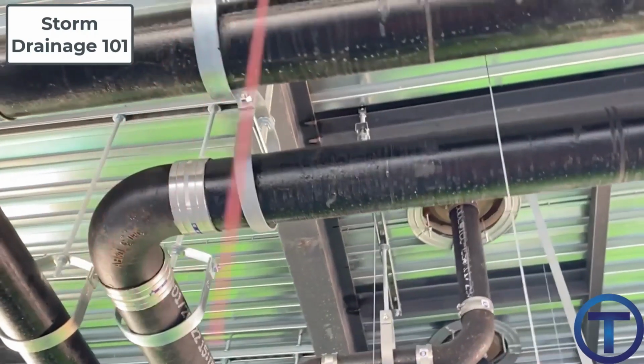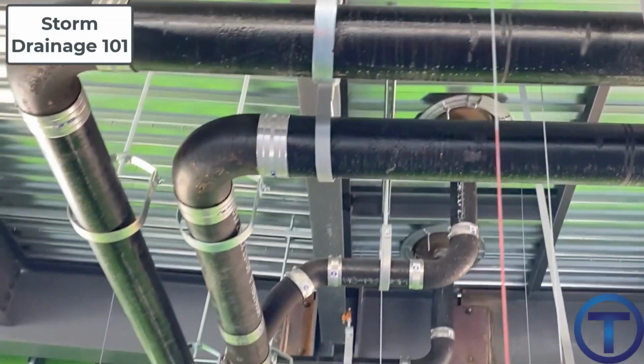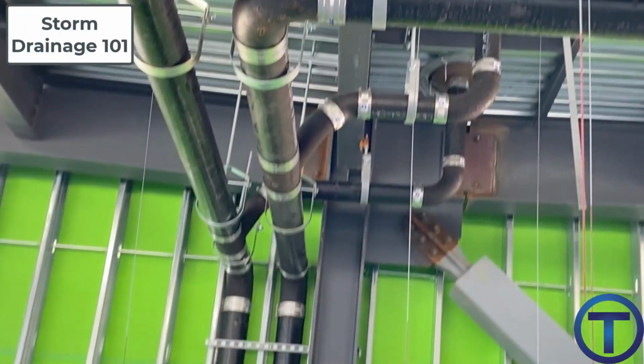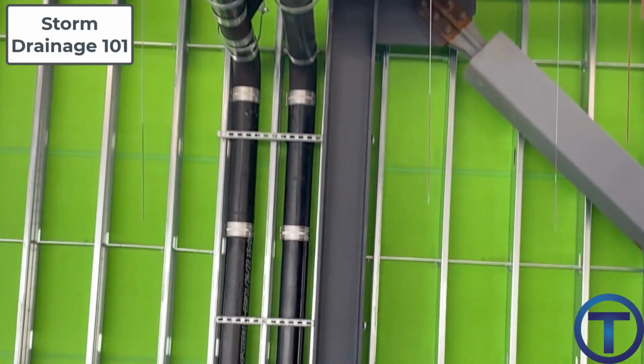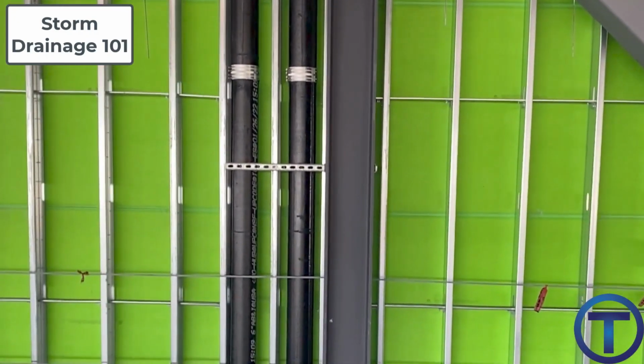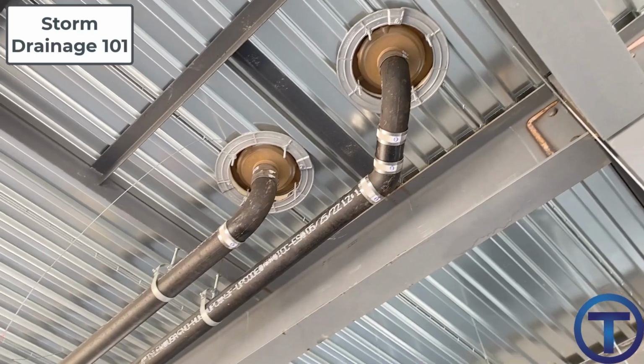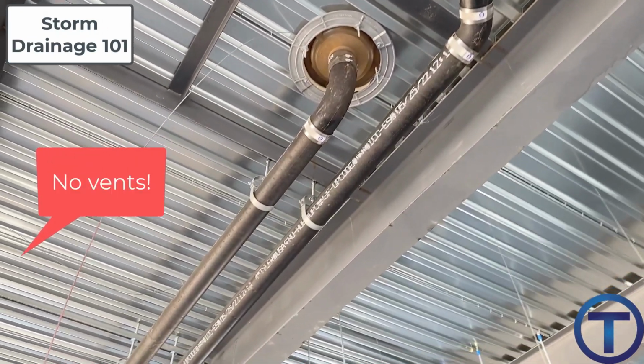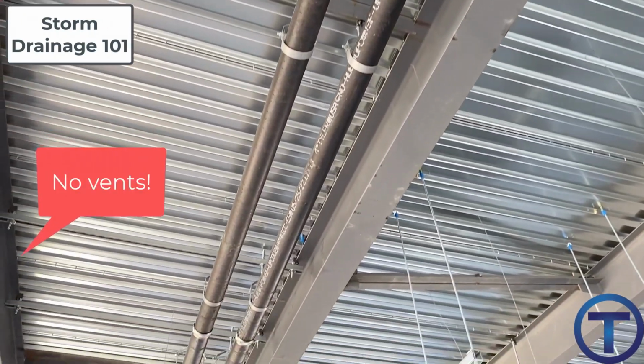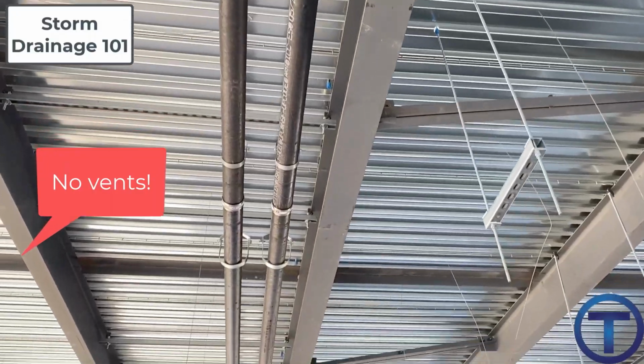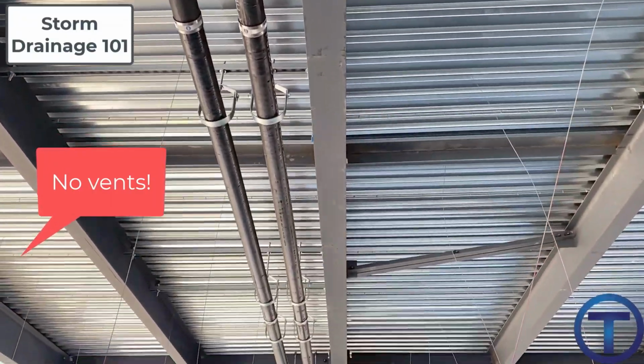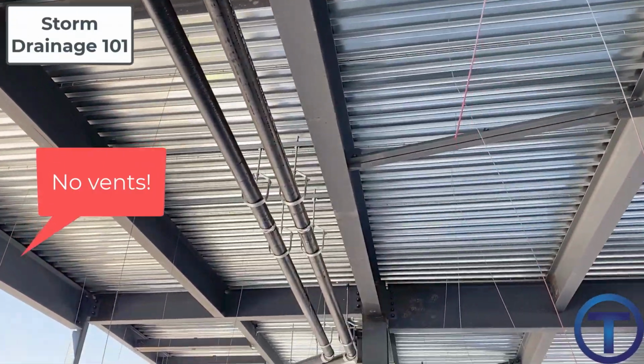So in this way, roof drains or storm drainage are very much like drainage, waste, and vent. However, they are different than drainage, waste, and vent because we can drop the last part, venting. There is no venting required for storm drainage. It's just one big, wide open pipe that opens and conveys that water out of the building.